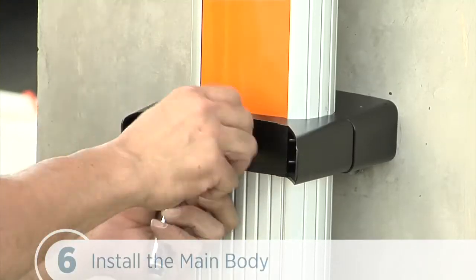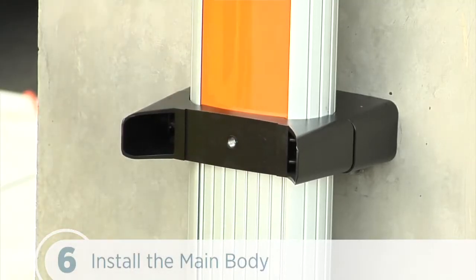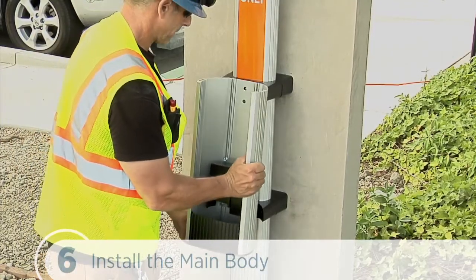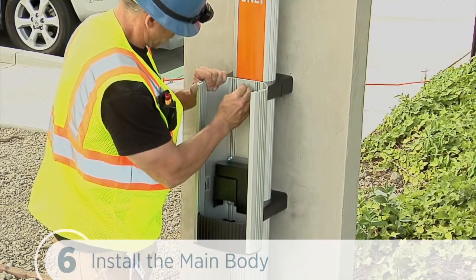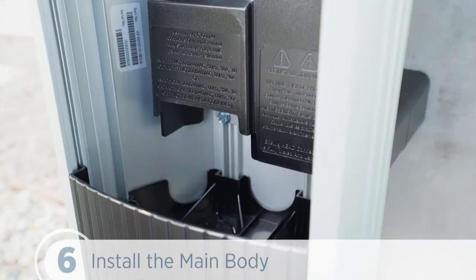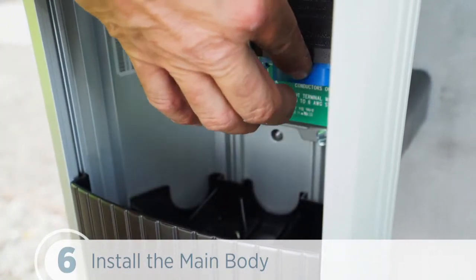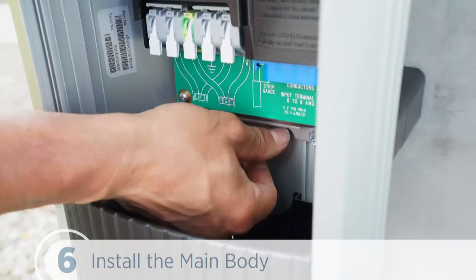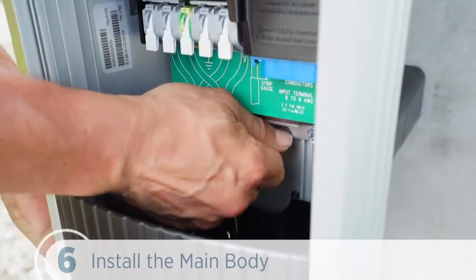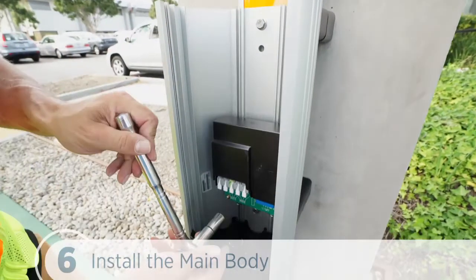To mount the main body, we first need to remove the 3/8-16 by ¾-inch flange bolts from the rear brackets and hold onto them. Next, we position the main body so that the top hole aligns with the top retractor bracket. Re-insert a flange bolt into the top hole and finger tighten. To mount the second flange bolt, expose the pre-drilled hole location below the terminal block. We push the tab on the terminal block to release the cover plate, then slide the cover plate upwards until it stays in position. And reinsert the other flange bolt into the lower mounting hole. Now we can tighten both flange bolts to 50 inch-pounds or 5.7 Newton-meters.